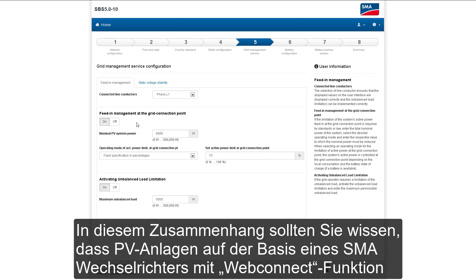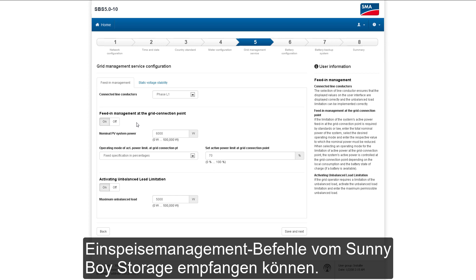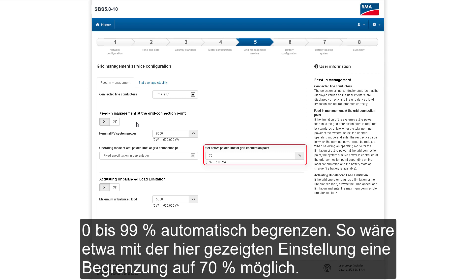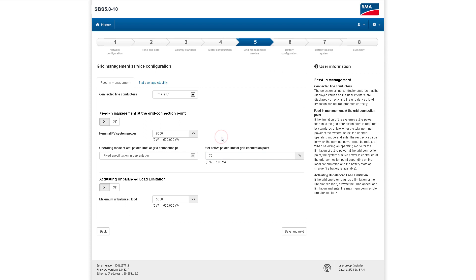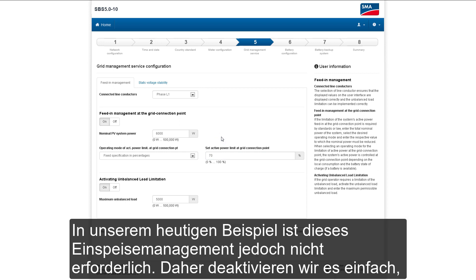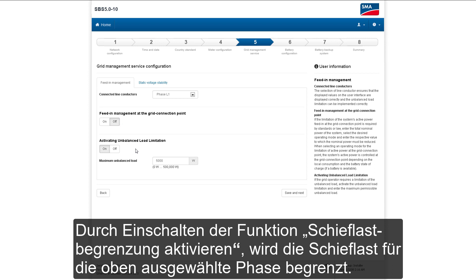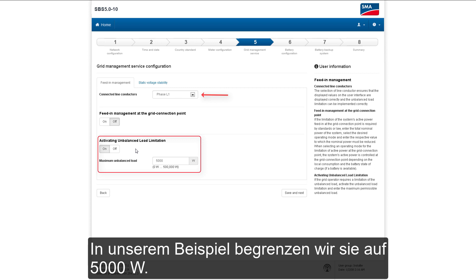PV systems based on SMA inverters with WebConnect functionalities are able to receive feed-in management commands from the Sunny Boy Storage directly. For example, the Sunny Boy Storage could automatically limit the power flow to the grid connection point in a range from 0% to 99%. Limiting to 70% would be possible with the setting chosen here. In our today's example, this feed-in management is not required, so we simply deactivate it by selecting Off. By choosing Activate Unbalanced Load Limitation, we can limit the unbalanced load for the selected phase — in our example, we limit to 5000 Watt.